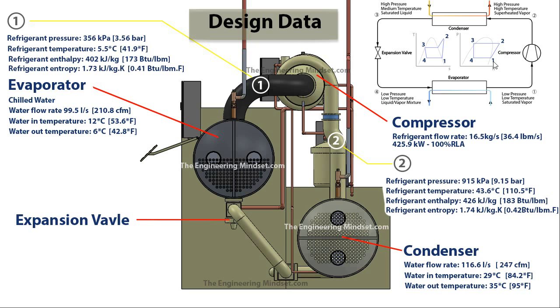Moving on to point two, located just after the compressor, we know the enthalpy is going to increase because it has moved along the axis, and entropy is going to increase as well since it's not a straight line. Temperature and pressure also increase. At point two, the pressure has increased from 356 to 915 kilopascals (9.15 bar), the temperature has increased from 5.5°C to 43.6°C (110.5°F), and both enthalpy and entropy have also increased.